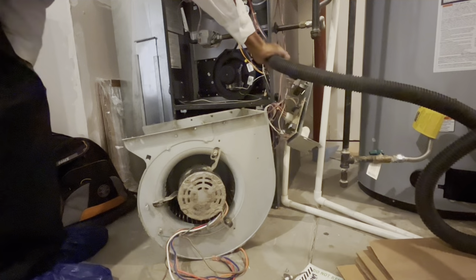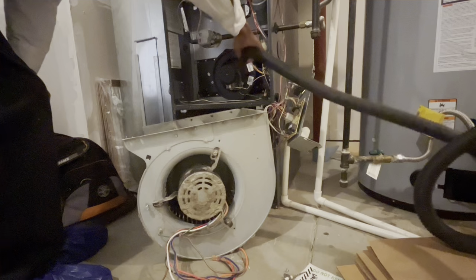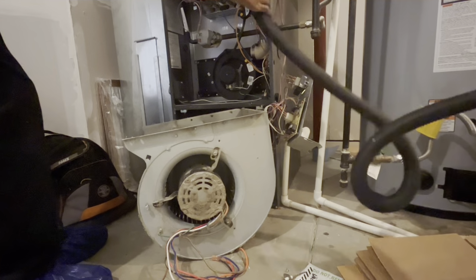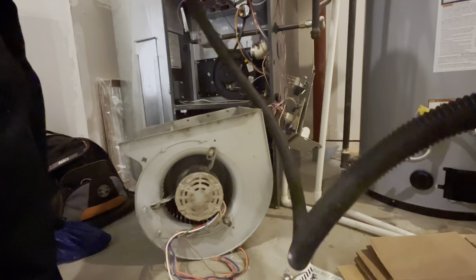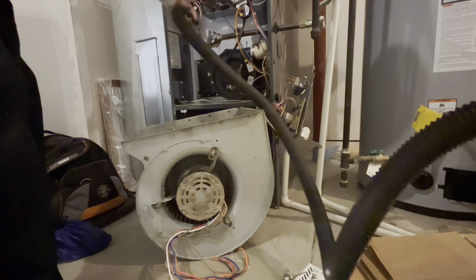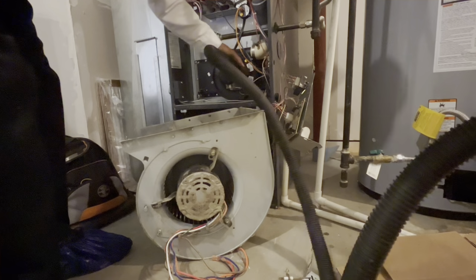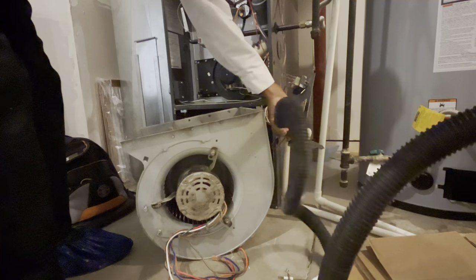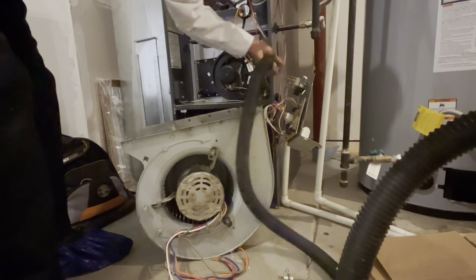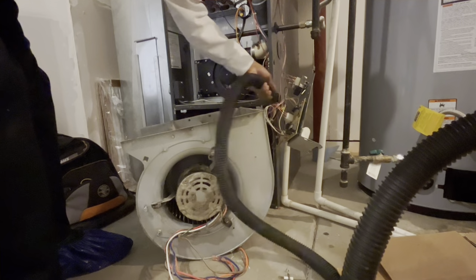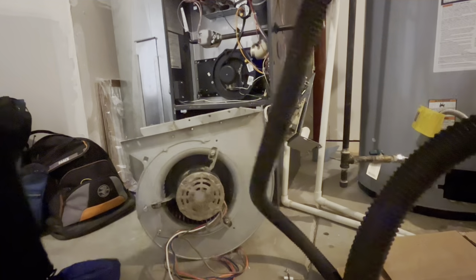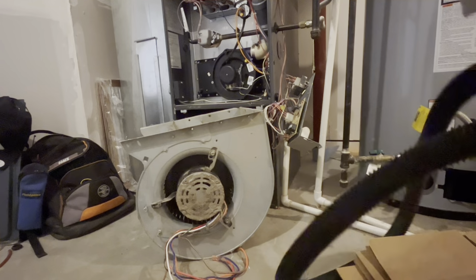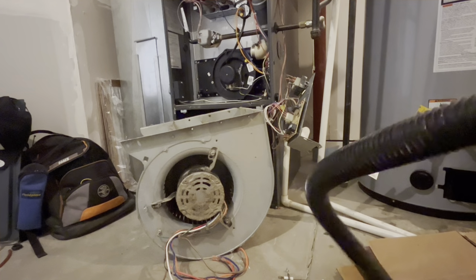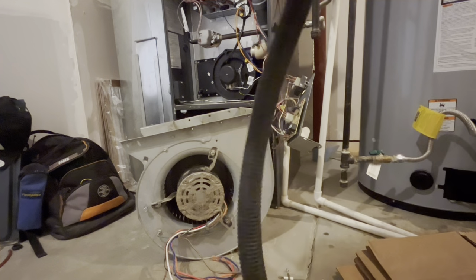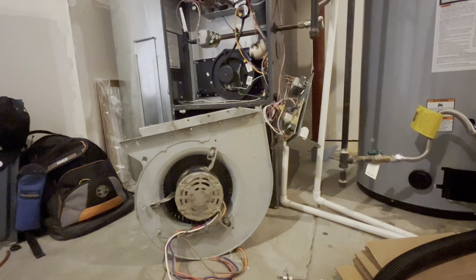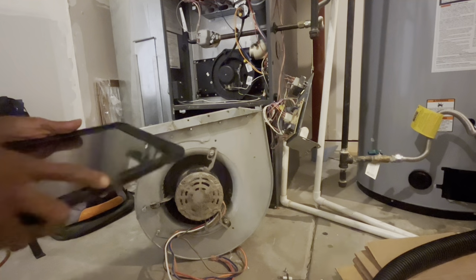So I'm taking my shop vac out. I'm blowing all that dirt and debris off of the circuit board and out of the burners. Sometimes I will take the whole burner cabinet out and clean it by hand, but in this case I felt that it was okay just to blow the air out of it. And I find that having a shop vac does a really good job for this. So I did that, and then I went ahead and turned the shop vac in the opposite direction to actually, I believe, start sucking the dirt off that motor once I start getting it all out.